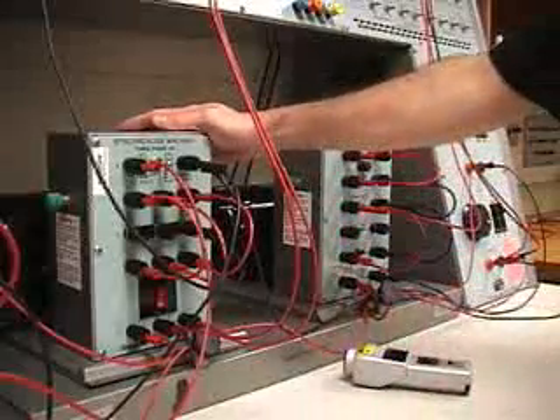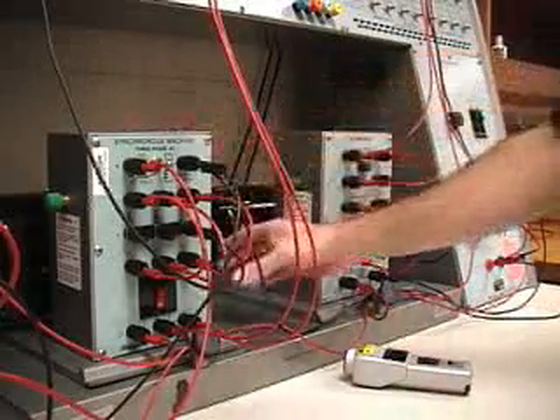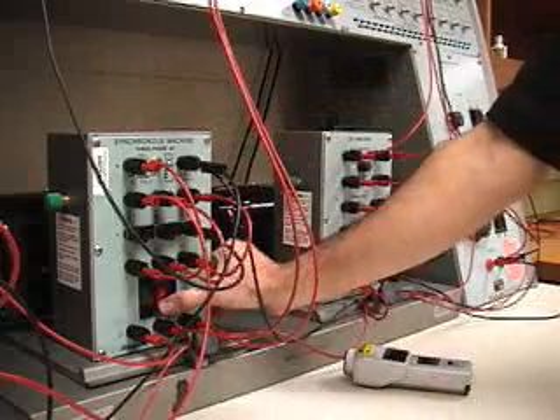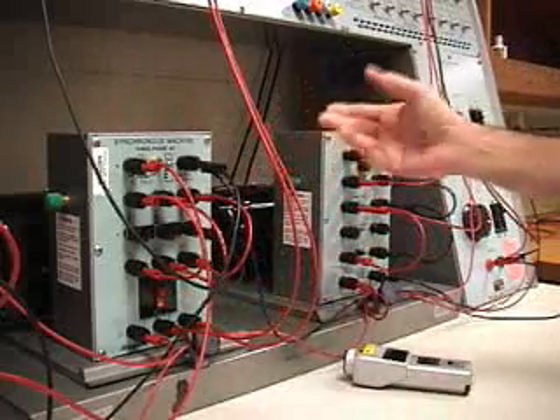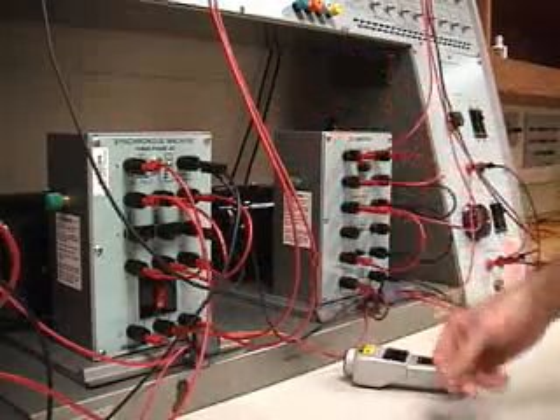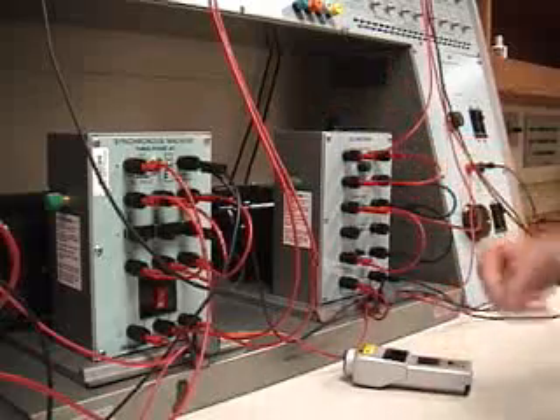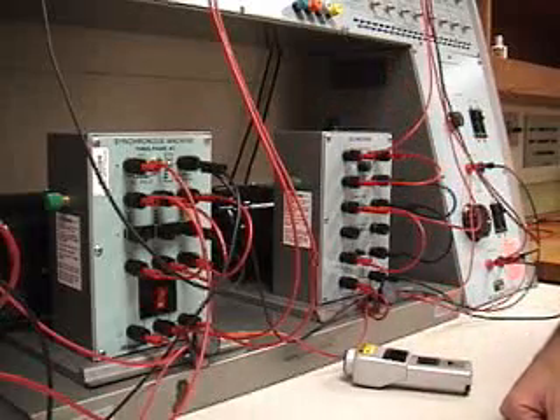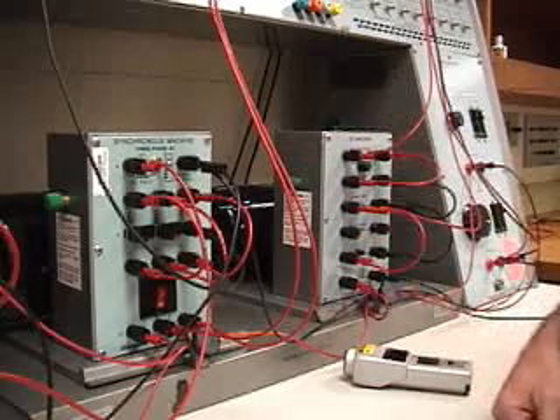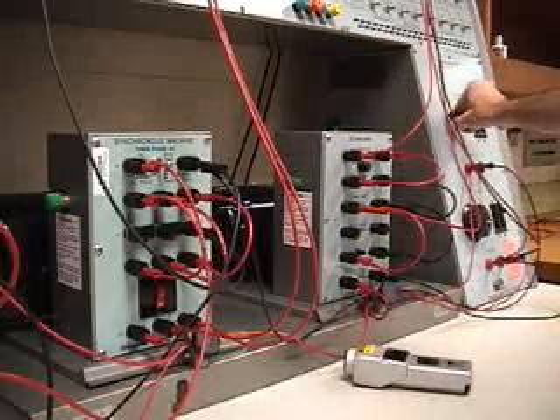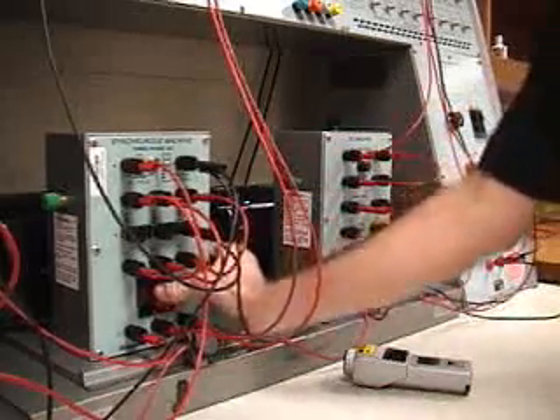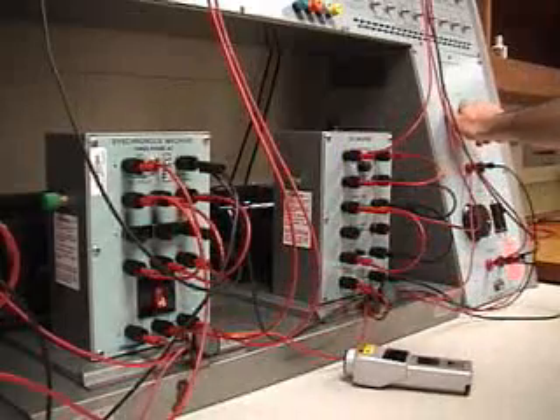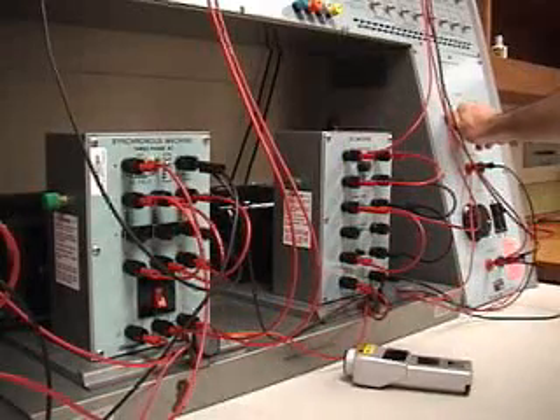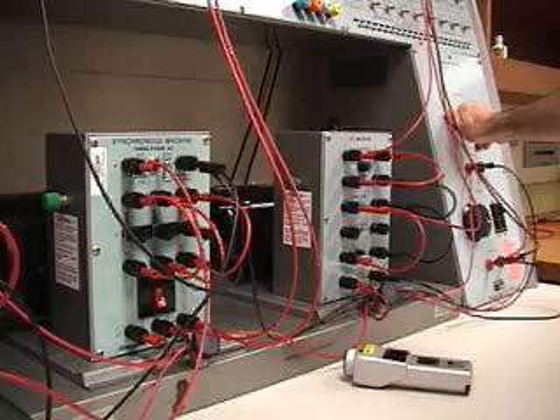In the startup of the three-phase synchronous generator, again the circuit breaker should be off initially and the load should be at 0 value for when the circuit breaker is turned on. The synchronous generator, before the load is connected, once you are driving it, you should adjust the excitation to get the voltage operating at a satisfactory level for the load before switching the load on.